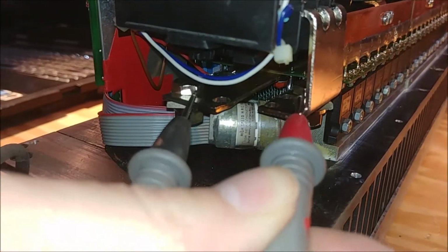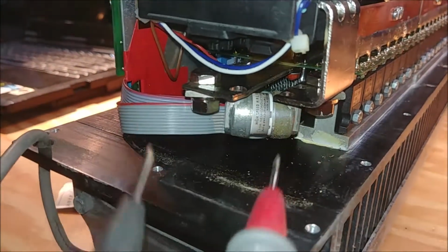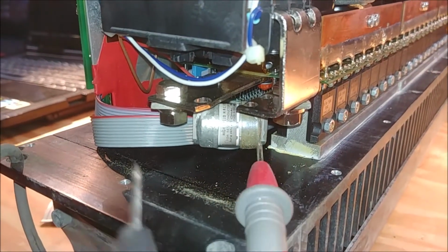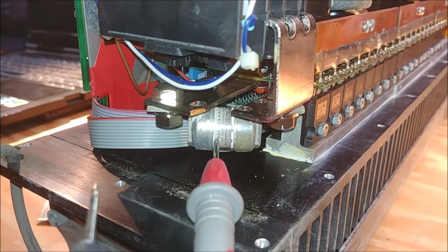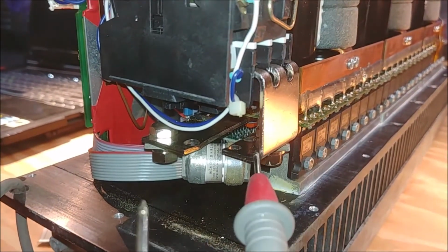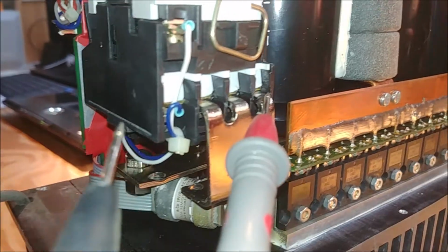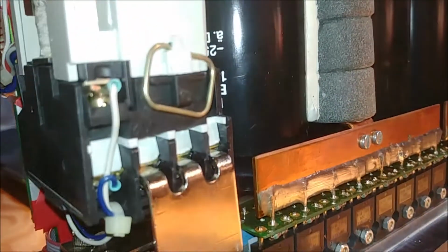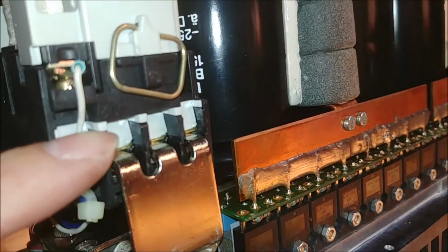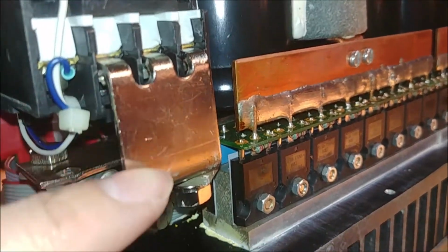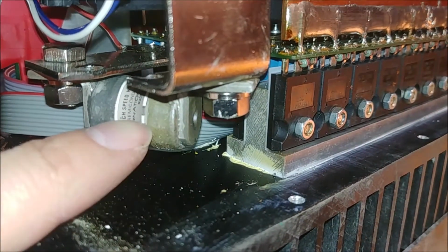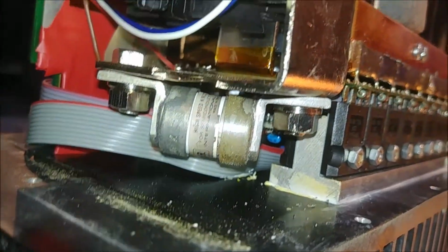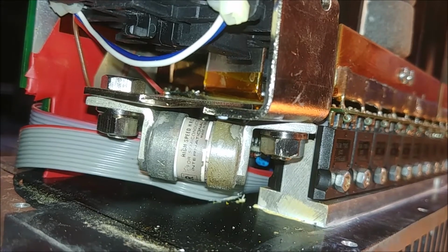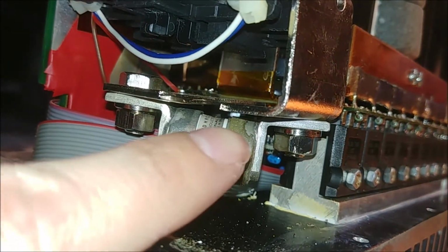Now I don't know, it's one of those chicken or the egg things - I don't know if this got so hot that it died and opened, but transferred heat up here and caused it to melt the contactor, or if the contactor got so hot that it transferred heat down here and caused the fuse to go, because it's definitely this side of the fuse that looks like it got much hotter than the other side. I mean, it got hot enough that it actually flowed solder.